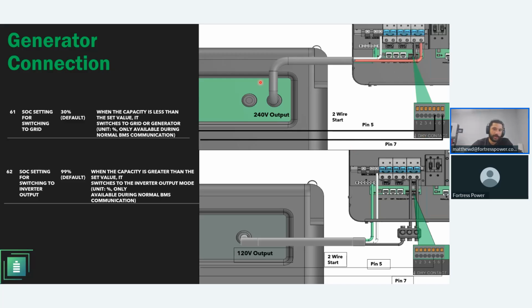If you have a 240 volt generator, then you would land 240 line 1 and line 2 on the generator breaker. Now, it is very important that if you're running the application at 120 single phase and you want to tie in a generator, then the generator also has to be 120 single phase. You can't have a 240 generator and run the inverter at 120 volt load output, right? Generator has to be 120, inverter has to be 120. If the generator is 120/240, then the inverter has to be 120/240, right? And then you would use the settings, which would be setting 61 and setting 62.